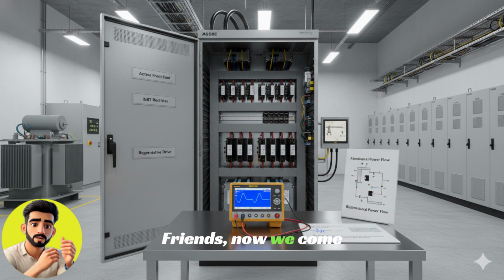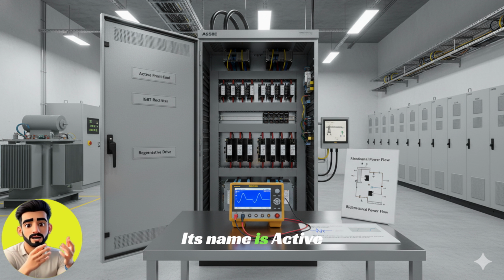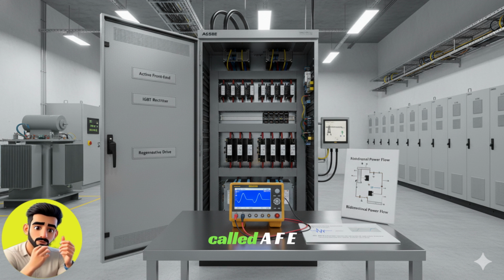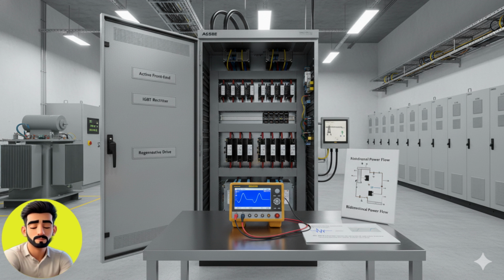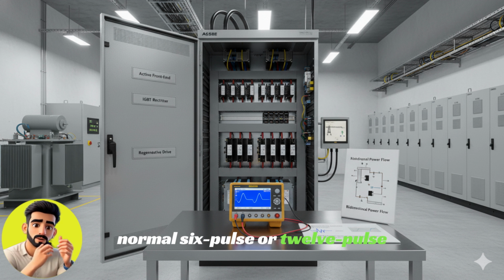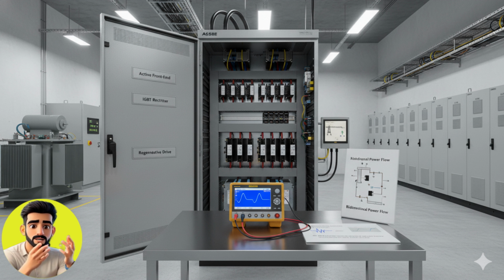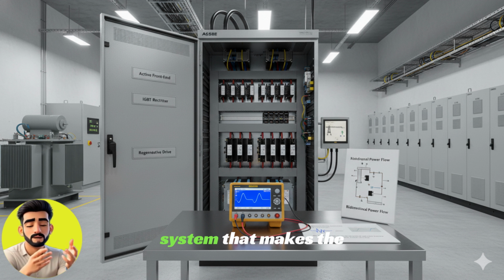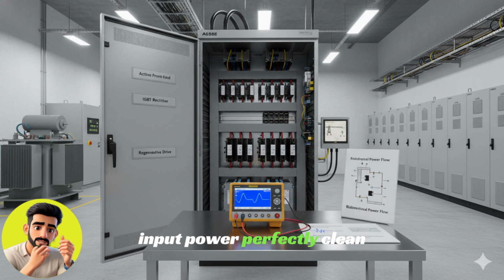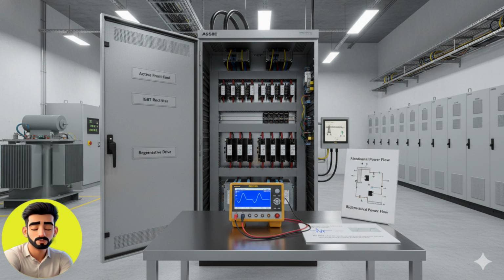Friends, now we come to the most advanced solution in harmonics. Its name is Active Front-End Drive, also called AFE drive for short. AFE drive is the next level of VSD technology. It is not a normal 6-pulse or 12-pulse system. It is a smart and fully controlled rectifier system that makes the input power perfectly clean and reduces harmonics to near zero. Let's understand in simple language what the actual function of AFE drive is.